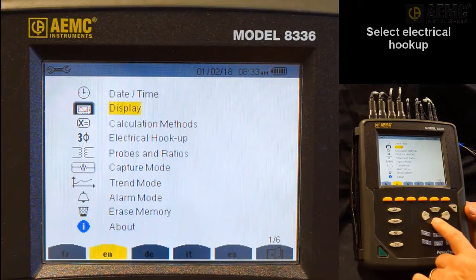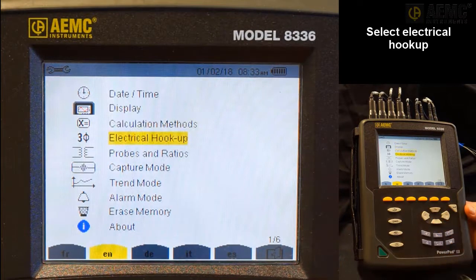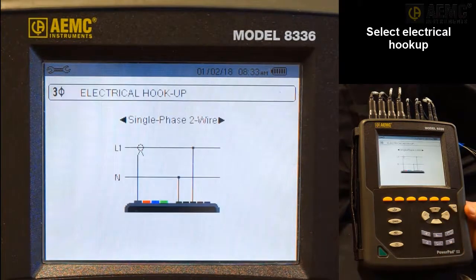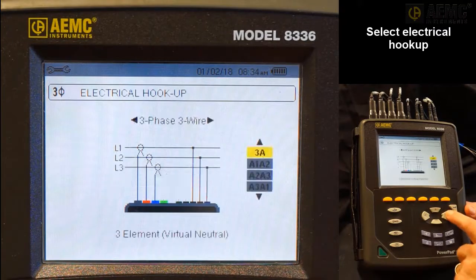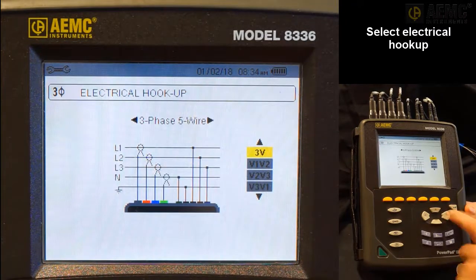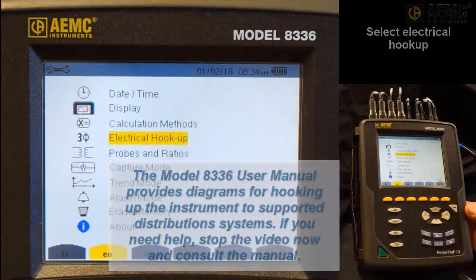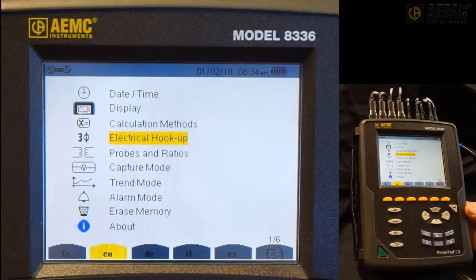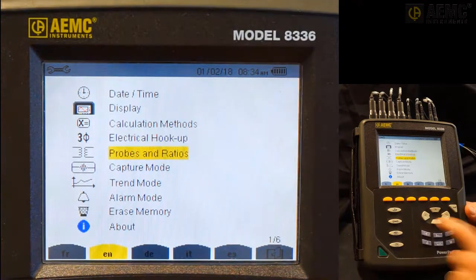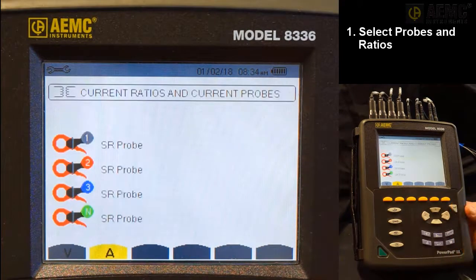Use the arrows to navigate to and highlight electrical hookup, then press Enter. In our example, we will connect to a simulation of a three-phase, five-wire hookup, so we will select this option and then press Enter. You are now returned to the configuration options screen. Use the arrows to navigate to probes and ratios, and press Enter.